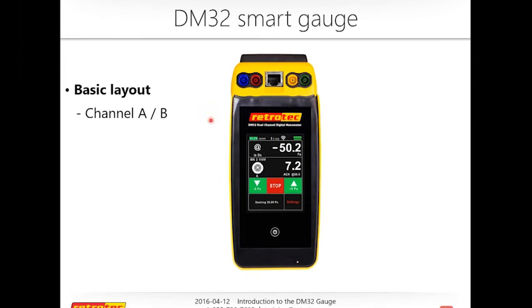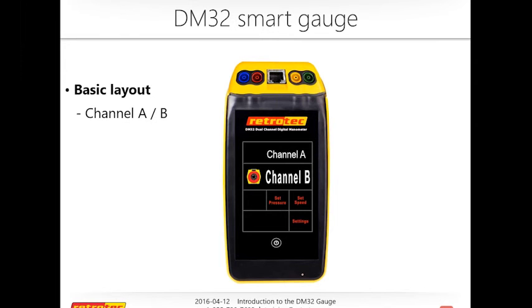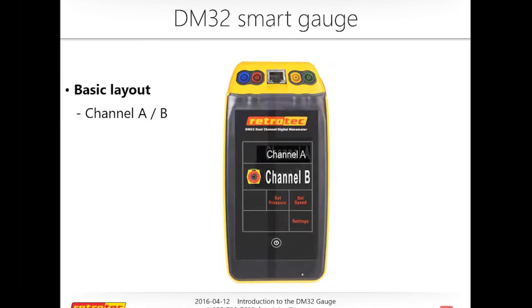Here are the physical connections and here are the digital connections. Let's break it up and get more in depth into the difference between channel A and channel B. As you can see, these two gauges are essentially a single gauge that has two pressure manometers, two differential gauges, connected only by a battery. That's extremely important to note, because later I'll explain how you can test both gauges by referencing them against each other. So that single gauge has two channels, which are essentially two different manometers.